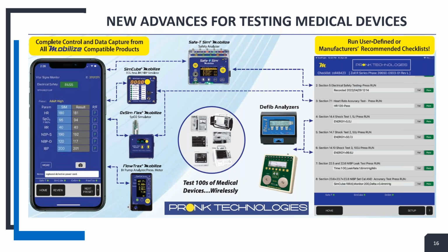All right, so what does that step need me to do? I need to set the defib analyzer to 50 ohms. So hit run. You won't be able to hear it, but it remotely sets the defib analyzer to the right impedance to do the measurements. Now we can hit pass and go on to the next test. For pacing tests on this particular device, I need to move the connections over to the pacing side, which is over here. So we can move the jacks, the leads, over to that so we can do our pacing tests.